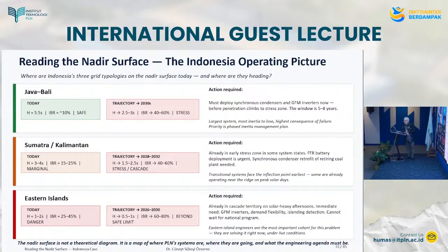Sumatra, Kalimantan today is between 3 and 4 seconds, 15 to 25% IBR resources. It's marginally safe zone, but by 2028 and 2032, which is not a long time away, the inertia constant can fall down to about 2 seconds, and the expected IBR is minimum 40% according to the forecast. It could be 60%, and it is going to be a stressed operational zone. The risk of cascading failures. Action required already in early distress zone in some system states.